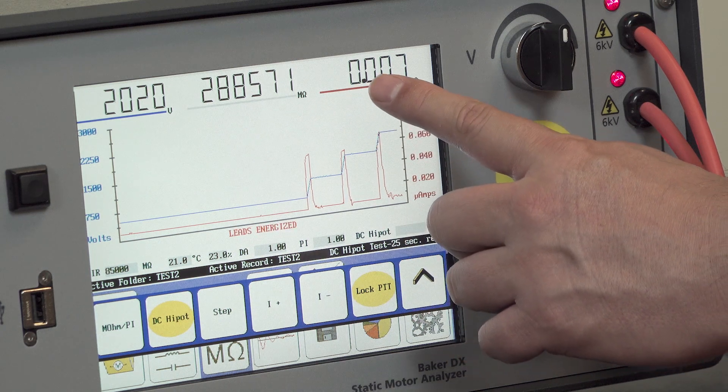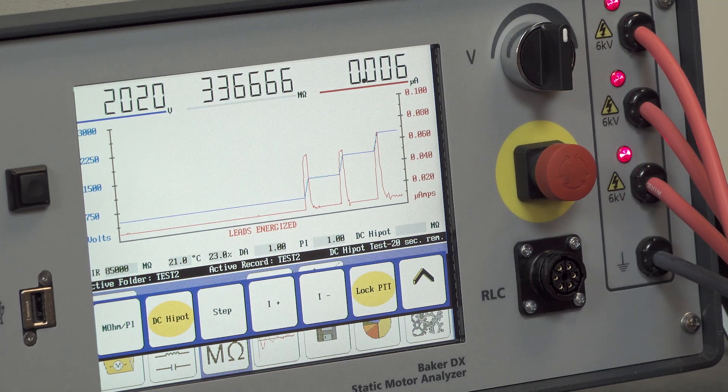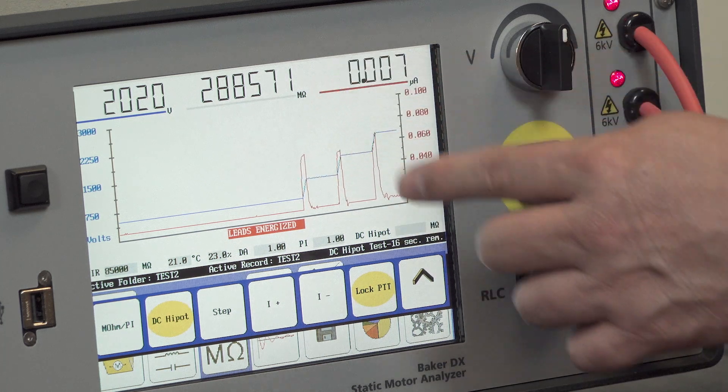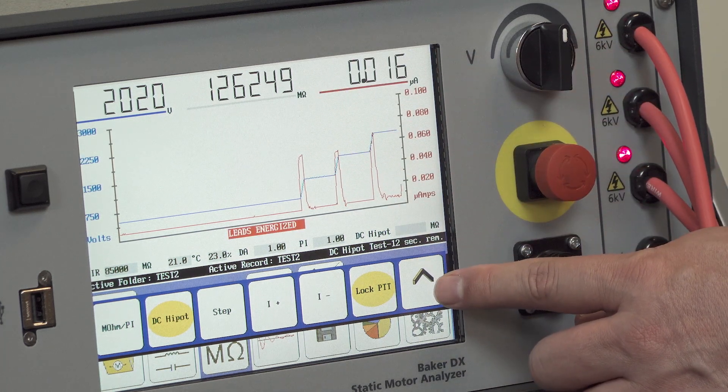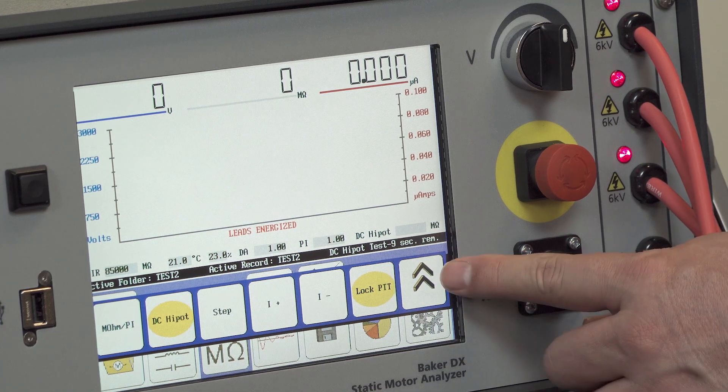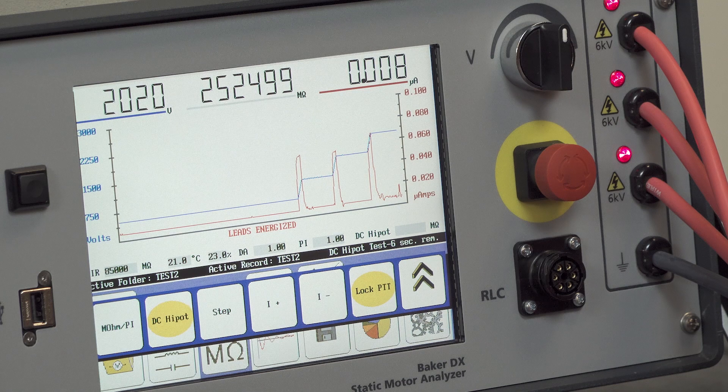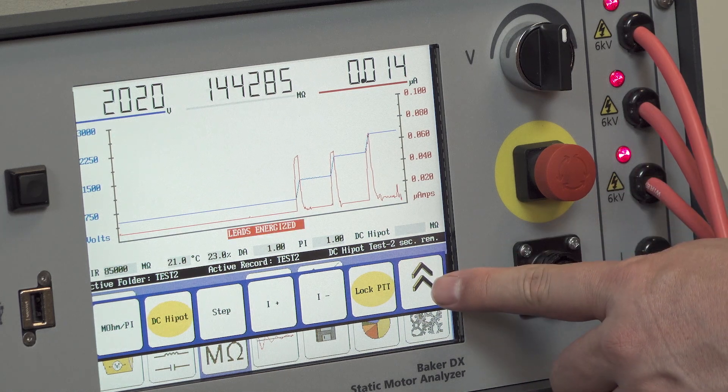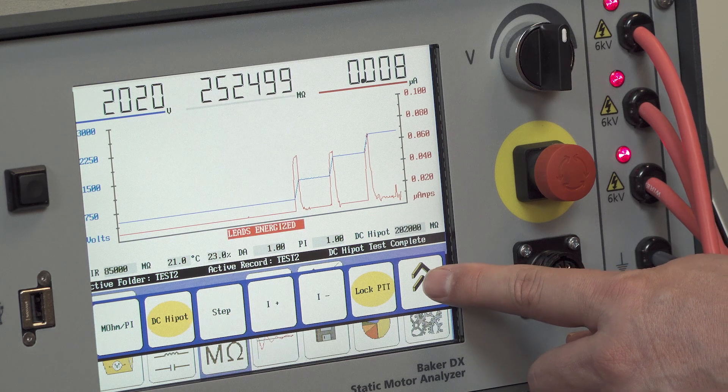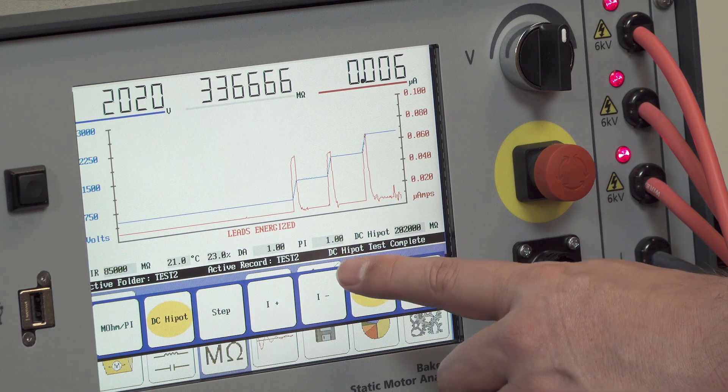As we were ramping, since we were going in small voltage increments, I was using the slow ramp. But you can also select a fast ramp during your ramp to achieve higher voltages more quickly. The rate of voltage change is defined in the user settings. Okay, now that we've achieved 60 seconds in the final step, DC hipot test is complete.